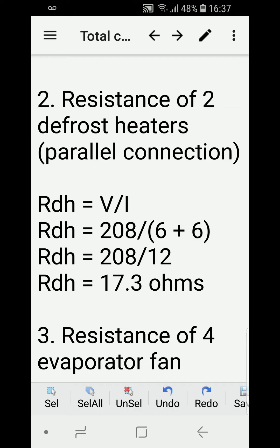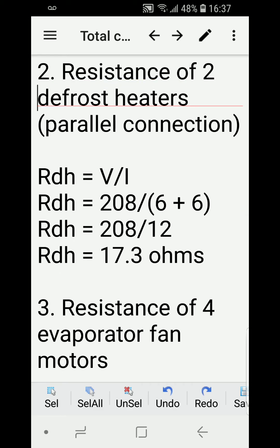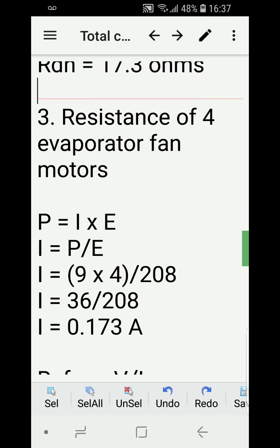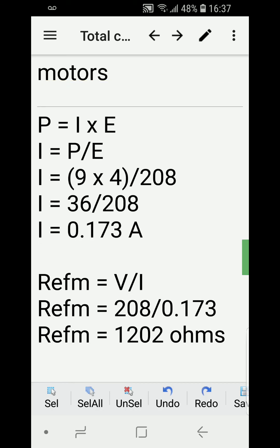Next, we calculate the resistance of the two defrost heaters. They are in a parallel connection, so we calculate 208 divided by (6 + 6), which is 208 divided by 12, giving us 17.3 ohms. Next, we calculate the resistance of the four evaporator fan motors.